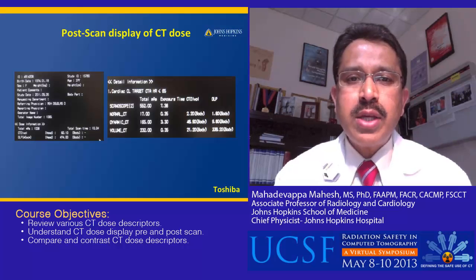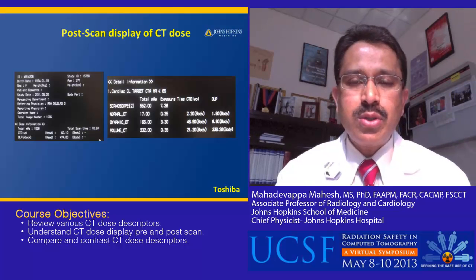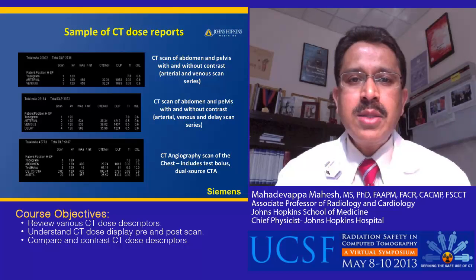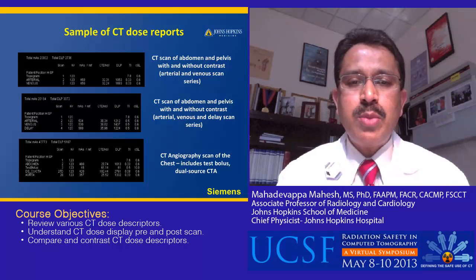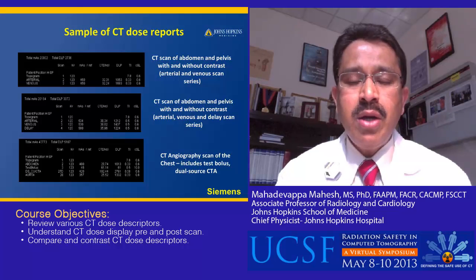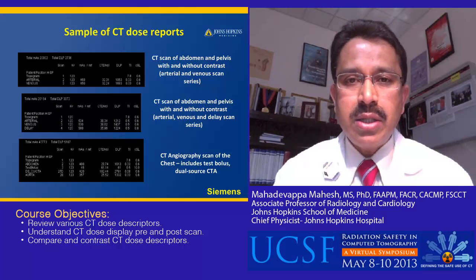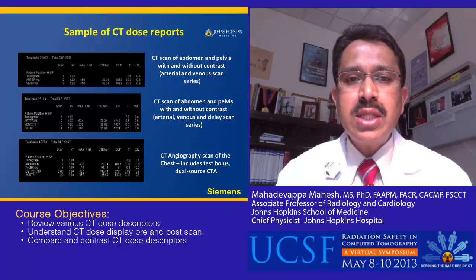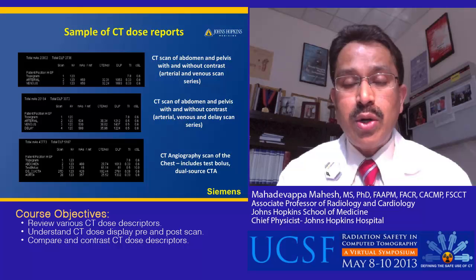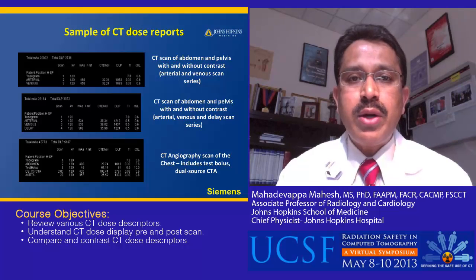Shown here is a sample post-scan display from a particular manufacturer. This dose report shows the total mAs value used in different scan series, along with the CTDIvol and the DLP. Another slide shows a different CT dose report from a different manufacturer, which is more detailed — providing not only the type of series done in the exam but also, for each line item, the selected kV, selected mA, along with the CTDIvol and DLP. This information can be used for calculating effective dose and organ doses, or for quality control purposes.